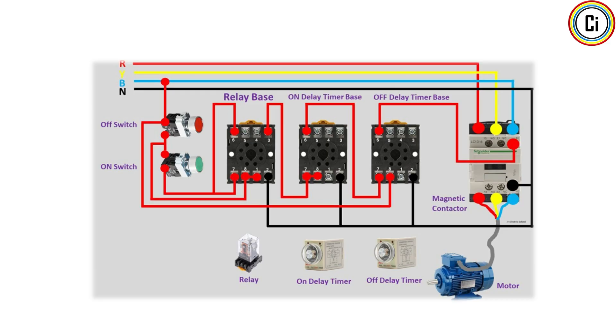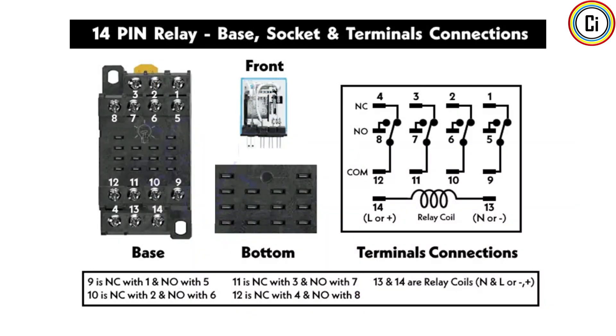A 14-pin relay is a multi-contact industrial relay with four changeover contacts, also called 4PDT — four pole double throw. Along with the two coil pins, it has 14 pins total. This allows you to control four independent circuits at the same time with just one signal.